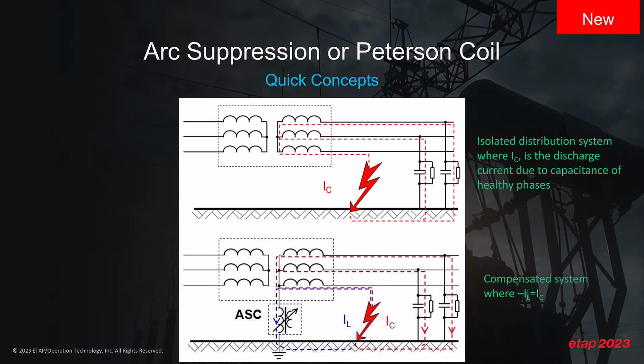the expectation is that the fault has to be cleared to avoid damage to the suppression coil in case of a sustained fault. Now, the inductance value of the arc suppression coil is therefore continuously monitored and adjusted such that if there is a fault current, IF, the inductance is able to exactly balance the capacitive current IC, creating a resonance ground. And that's the basic concept of an arc suppression coil. And of course, it's been used in Europe for the last couple of decades.